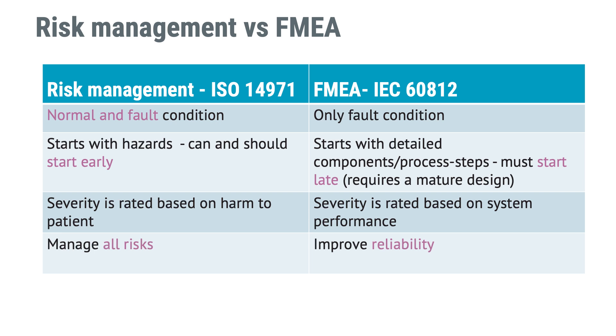The last major difference I would like to bring up is that ISO 14971 risk management is a very comprehensive approach that will address and manage all risks related to a medical device. There are some minor exceptions, so using the word 'all' is a strong expression, but as a rule of thumb it does hold water. FMEA, on the other hand, is a reliability tool which by definition does not include all risks — but if the safety of your system is dependent on reliability, for example in the case of a life-supporting medical device, using FMEA may be a good idea to achieve reliability and thereby also safety.